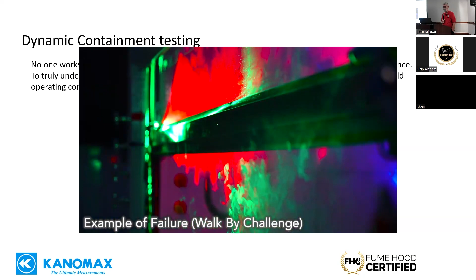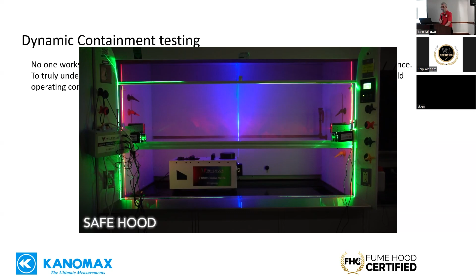So how do the challenges tell you if your hood is or isn't containing? Well, do you see green when somebody walks by the hood? Do you see green when you move the sash quickly? Do you see any green when the lab door opens and the room pressure changes? Do you see any green when you pull items out of the hood? If you can see green, that's loss of containment. Your hood might have a problem and should be repaired. If you don't see any green, well, you can be certain that your hood is performing safely.